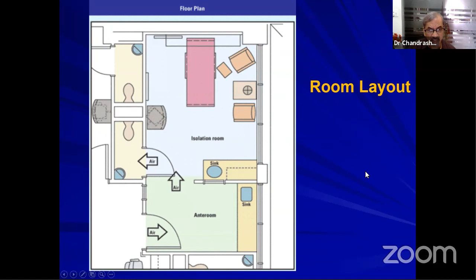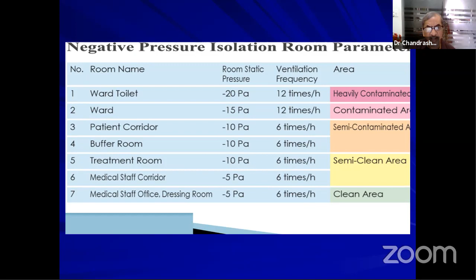So this is the typical layout of an isolation room, where we need an anteroom and an isolation facility. And nowadays, in the various wards we are dealing with, we have these kinds of pressures. The ward toilet is the highest, where we have at least 12 air changes per hour. These are heavily contaminated and contaminated air. The patient and buffer rooms are semi-contaminated, where we have 6 air changes and minus 10 Pascal. The treatment room is a semi-clean area where we have minus 10, and the medical staff corridor or other area has minus 5 Pascal. This is the general standard. Even ISHRAE or ASHRAE recommend it.